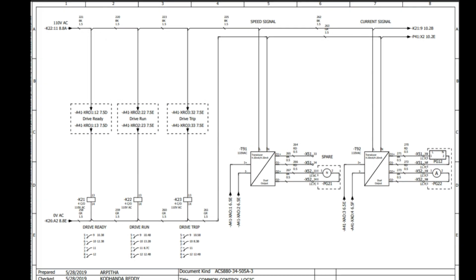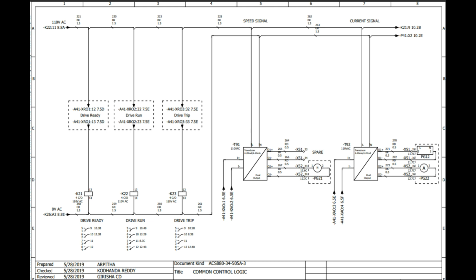This is a continuation of the previous page, that is the common control logic page. Here you can see again 110 volt on the top and 0 volt on the bottom. We'll start with the left hand side. The very first auxiliary contact you can see is drive ready, K21, K22 drive run, and K23 drive trip. What we have seen while discussing the control unit card, there we have seen those three relays. So K21, K22, K23 we have used in the previous page to understand how the system will work, and how this 110 volt will come and go to this auxiliary contact. Here you can see in the dotted box.